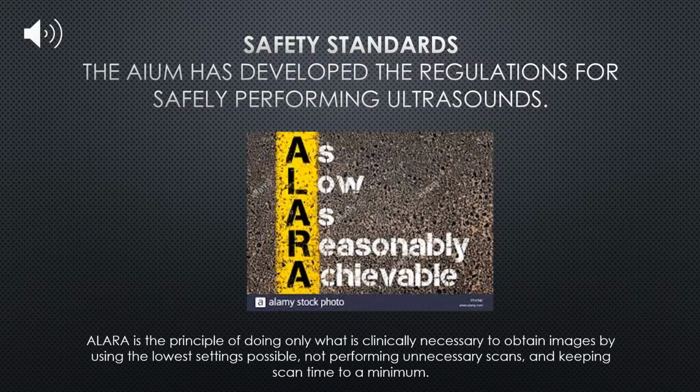Thankfully, there have been no recorded biological effects observed due to normal temperature rises less than or equal to 2 degrees Celsius above baseline with exposure duration up to 50 hours. The AIUM's statement on ultrasound safety indicates that the prudent use of the ALARA principle will make the benefits of ultrasound outweigh the potential risks, should there be any that are found.